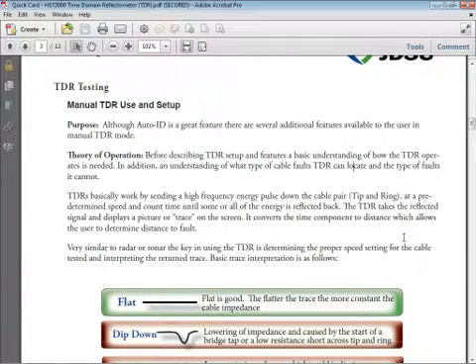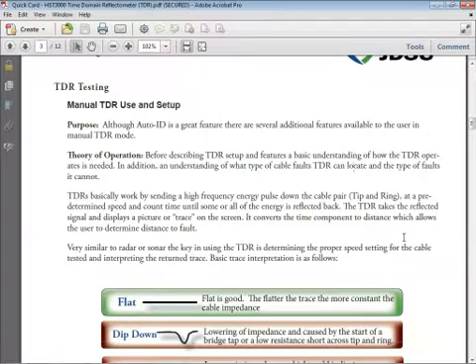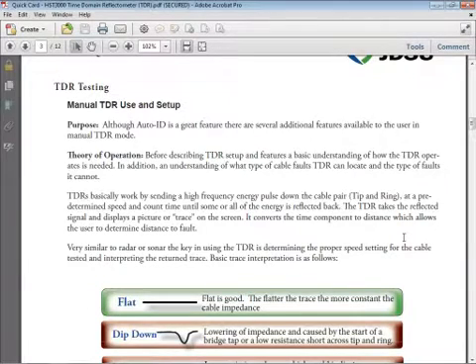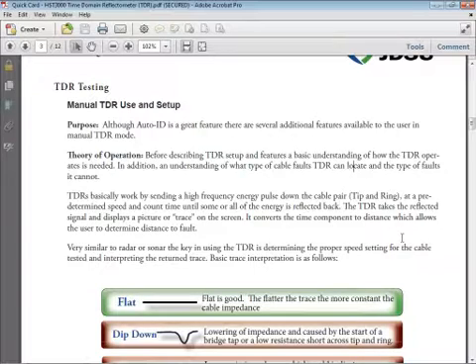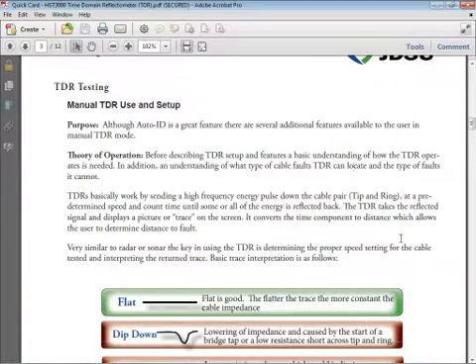That high frequency energy is looking for something called an impedance irregularity — that's a $25 word for a fault, or a major difference between tip and ring. When the energy hits the impedance irregularity, some of it is bounced back to the TDR — hence the radar or sonar analogy. Since the TDR knows how fast the energy is traveling, and since it has such an accurate clock built into it, all it does is a simple timed distance equation. So that's basically how they work.